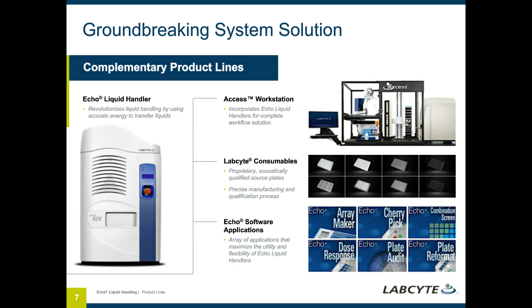The Echo liquid handlers themselves, I alluded to, come in really 2 different flavors. One is what we call the 55X, or that constitutes either the 555 or the 550, and is ejecting a droplet of 2.5 nanoliters. So this is ideal for your high throughput types of scenarios, for smaller reaction sizes, typically in the 0.05 to 1 microliter range, and supports both DMSO solutions as well as aqueous.